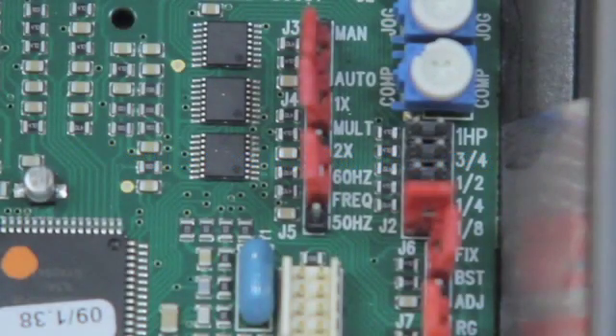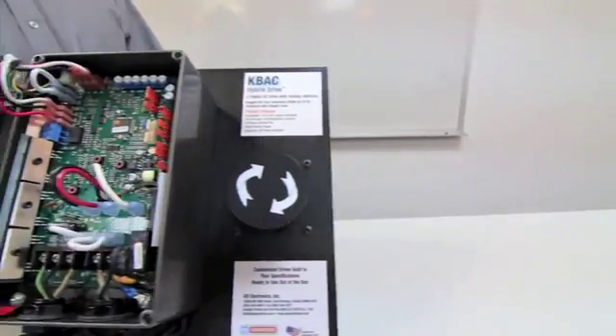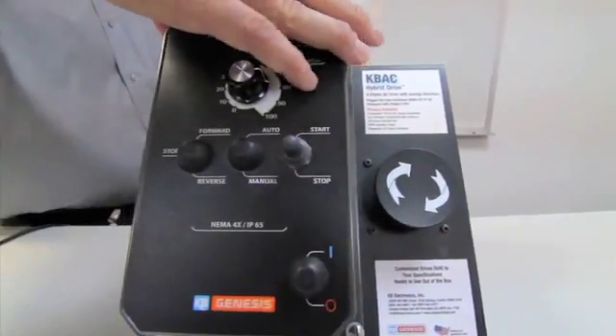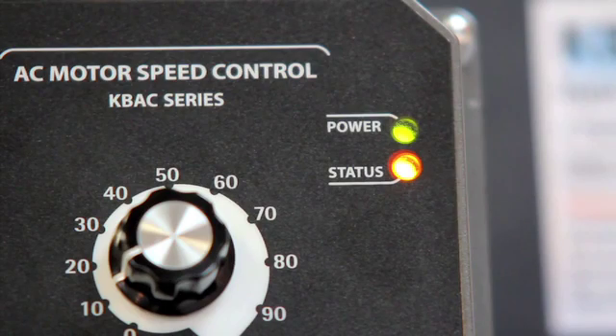Our standard factory jumper setting for motor frequency is 60 Hz. Move jumper J5 for 50 Hz European and IEC motors only. Close the cover and power the drive. The status LED light should be yellow and the power LED light should be green.